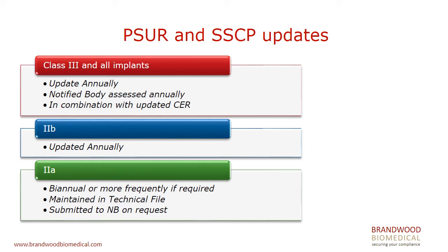For class 2B devices, these reports must be updated annually, but they don't have to be submitted to the notified body, although they can be, of course, inspected on audit. And for class 2A devices, at least every 2 years, or more frequently if it's appropriate. Again, maintained in the technical file, and again, must be available to be reviewed by the notified body on request.